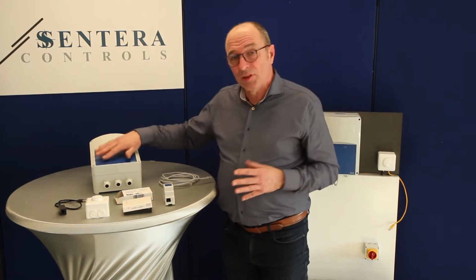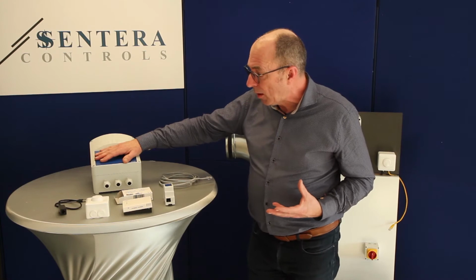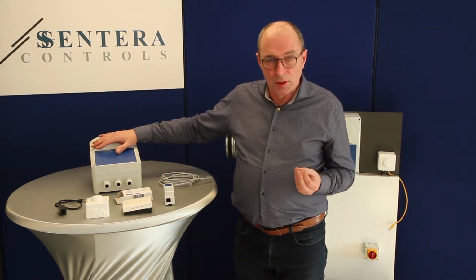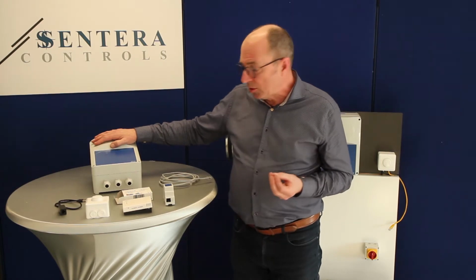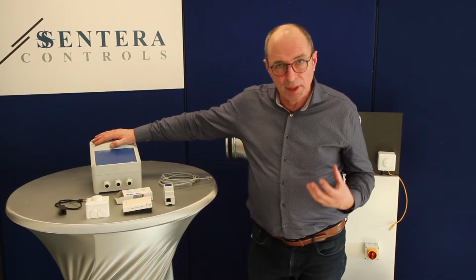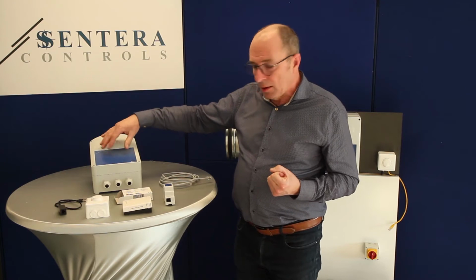In addition to the fact that it is a transformer fan speed controller, a technology that has already proven several decennia long to be very good for your motor, this device has a lot of extra options that are all located in the Modbus registers. At the end of the video, I'm going to take you inside the unit's processor to see which settings are all possible.